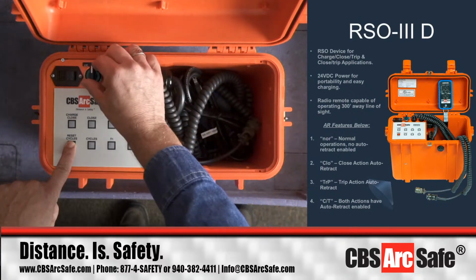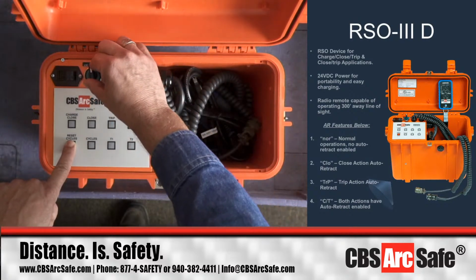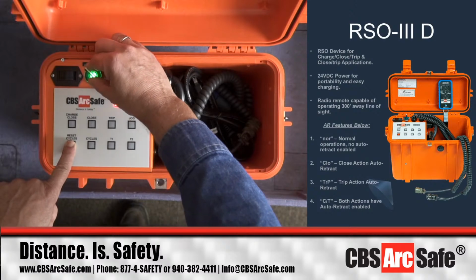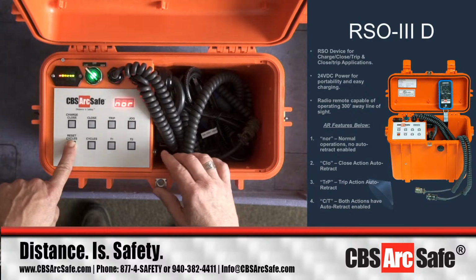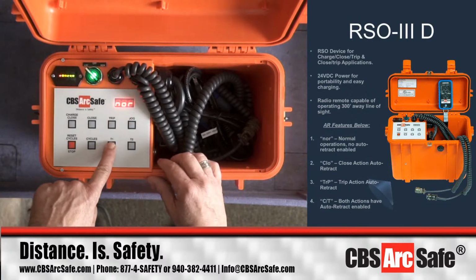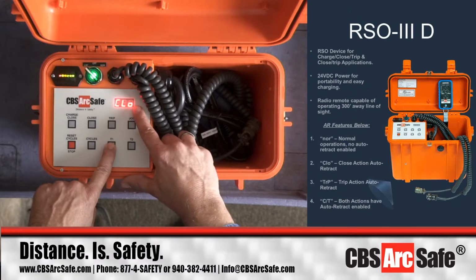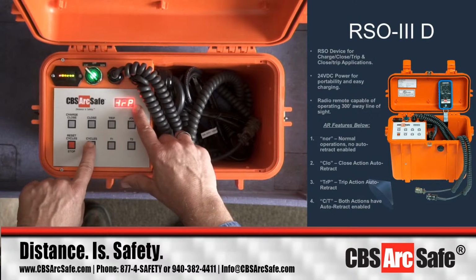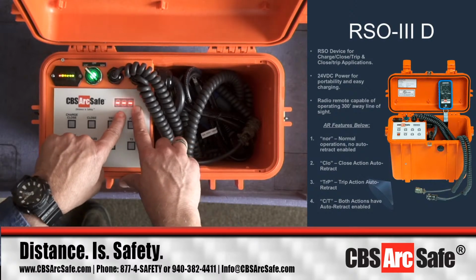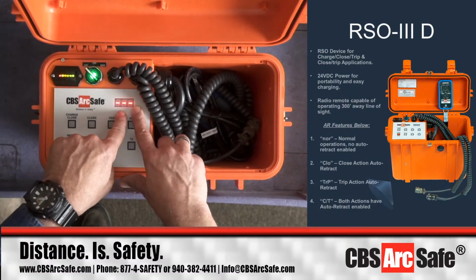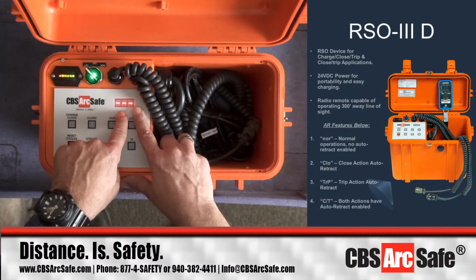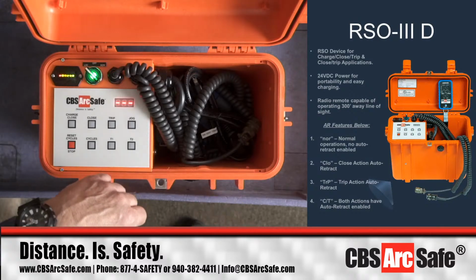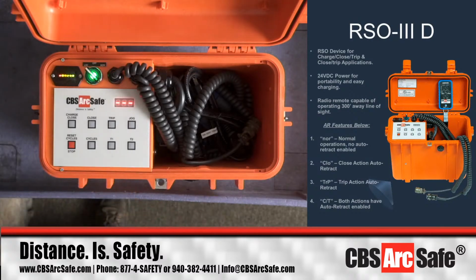And this has got lots of functionality in here, and I'm just going to run through this as we go. So you have to hold down the reset and cycles button to start with, and it's going to boot up, and then it's going to say normal. So you can have it for close here, or trip, or close trip, and we want it for just the trip. And to set that, we're going to hit the cycles button, and it's going to say ARO now, and now we're going to hit the reset button, and now it remembers that we want that functionality to be present for just the trip. ARO lets you know that you have selected automatic return.